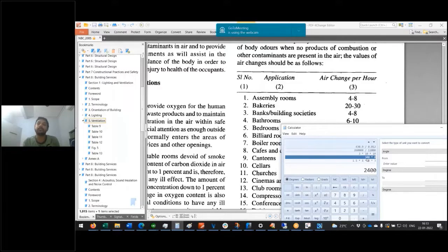Whereas this 2400... sorry to interrupt. This room volume, say 300 meter cube, that air has to be displaced through these exhaust fan ducts, right? There will be fresh air fans also. Suppose there are 4 fresh air fans and 4 exhaust fans. The same volume is displaced: fresh air comes in and exhaust pulls it out. So we can take the room volume alone, right? That will be correct.